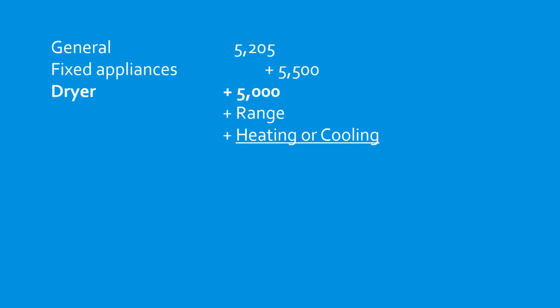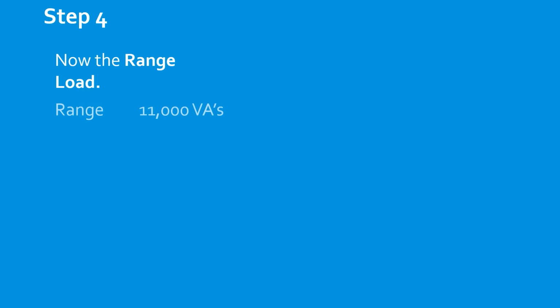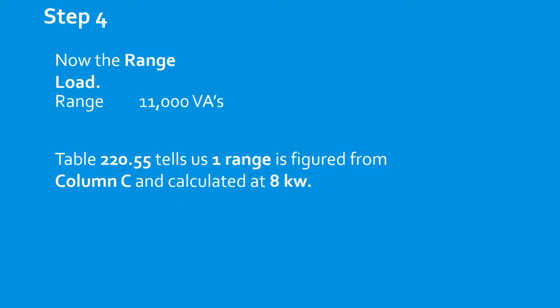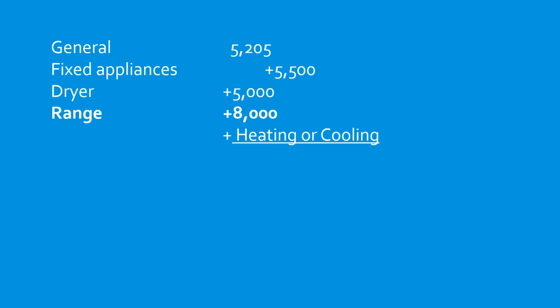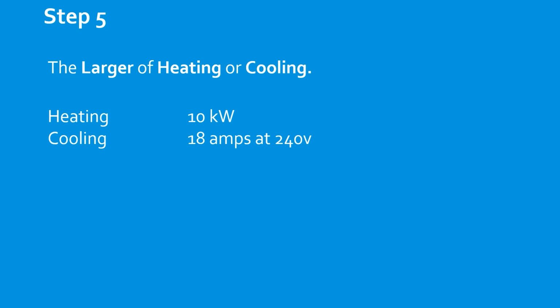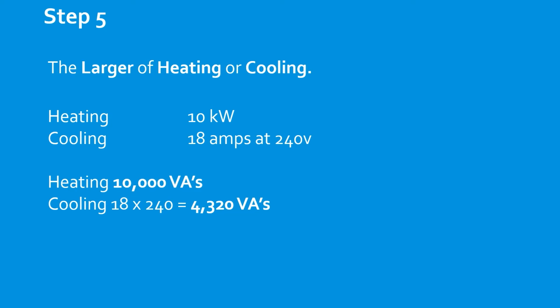Now let's do the range. Now the range load. In this case, we have an 11,000 VA range. In table 220.55, it tells us that one range figured from column C is calculated at 8 kW. So we add 8,000 to our load calculation. Now let's do the heating or cooling, the larger of the heating or cooling. Okay, so we have a 10 kW heat strip, and we have cooling at 18 amps at 240 volts. So our heating was 10,000. Our cooling after applying Ohm's law was only 4,320 VAs. And we're going to select the larger.